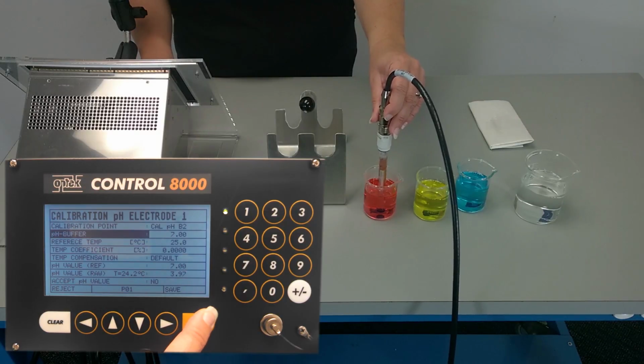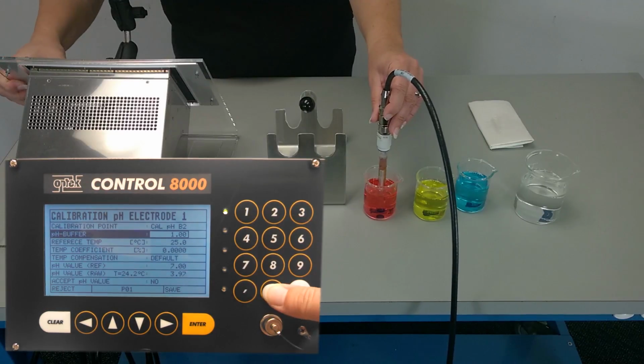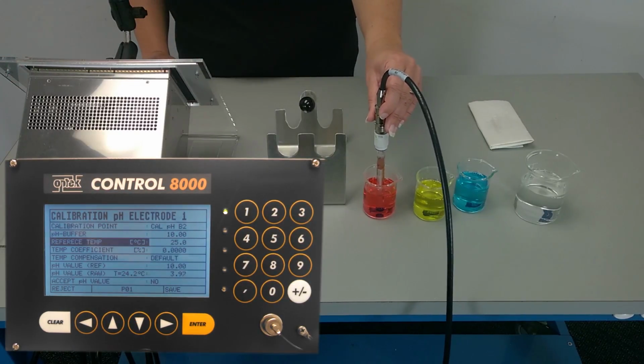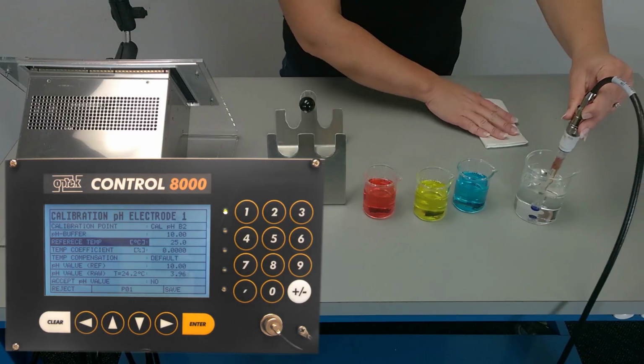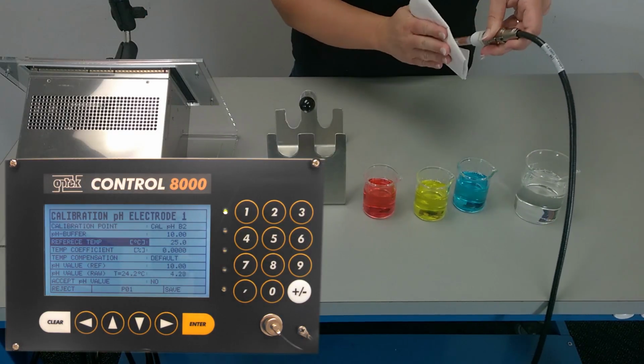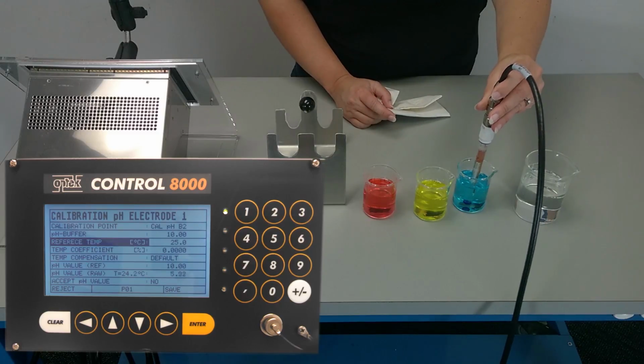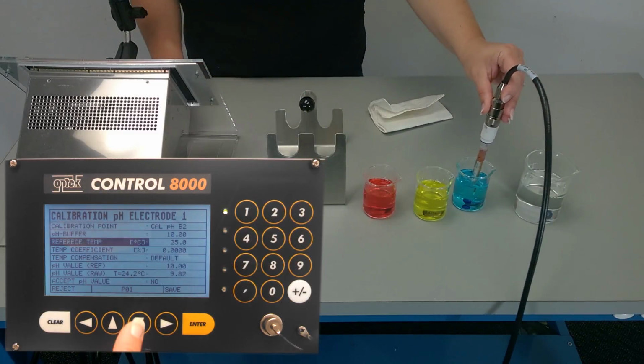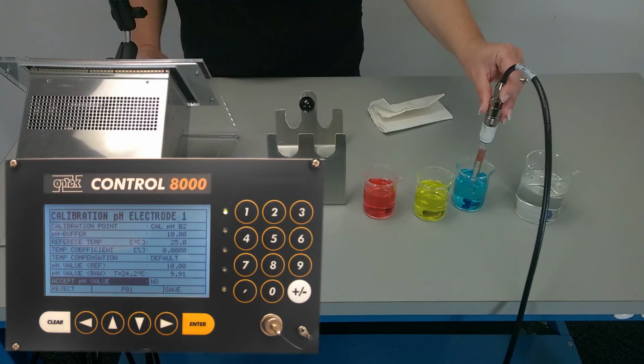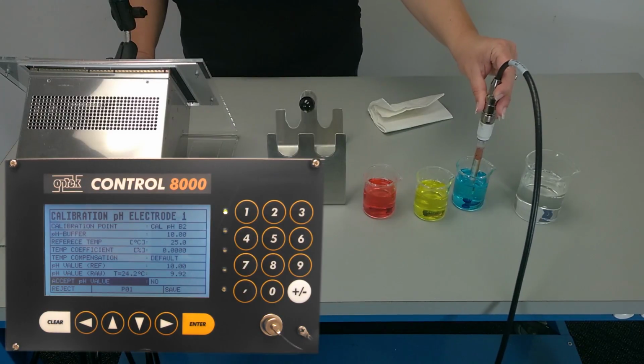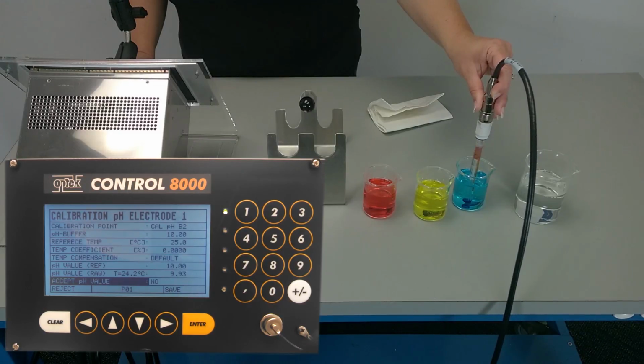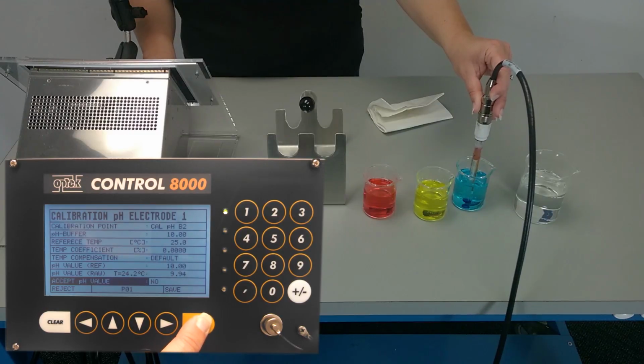We will be using a 10, so I will hit Enter and type in 10 on the keypad. Rinse the pH probe and then place it in the buffer 10. And the same procedure for the second buffer. I will scroll to accept pH value, and once the raw value is stabilized, I will select Enter and select Yes. So that is stable. I will hit Yes.